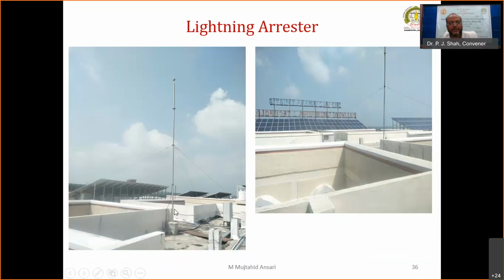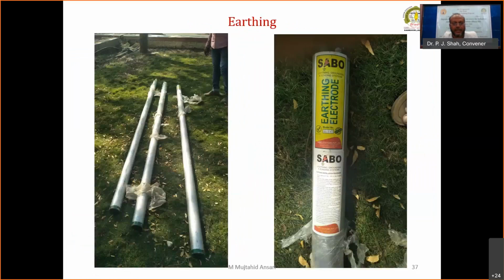Lightning arrestor is very much necessary. So here the lightning arrestor is connected, and the lightning arrestor has distinct earthing pits, two distinct earthing pits are there. It is also connected with the counter. If lightning strokes occur, the counter is going to increase, or the counter will show how many strokes have occurred during that period. So these are the lightning arrestors, and these are the earthing electrodes.